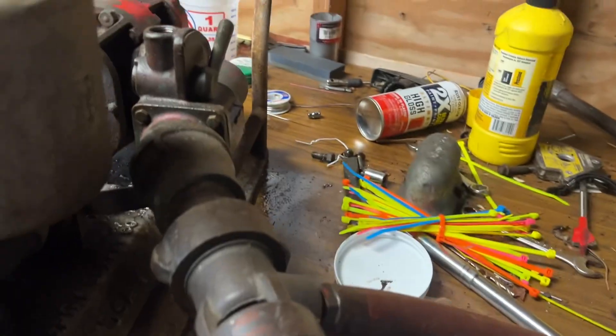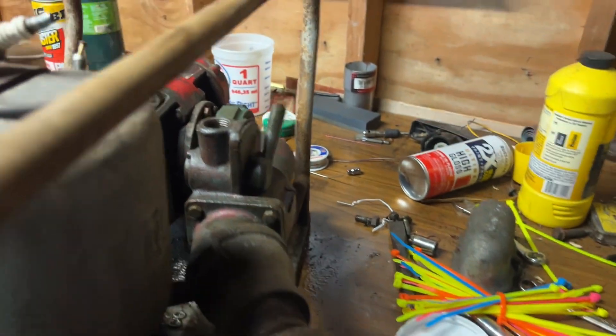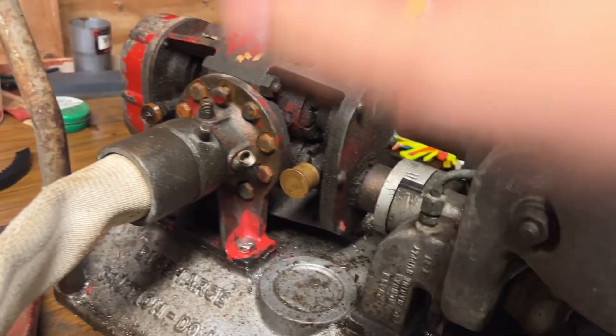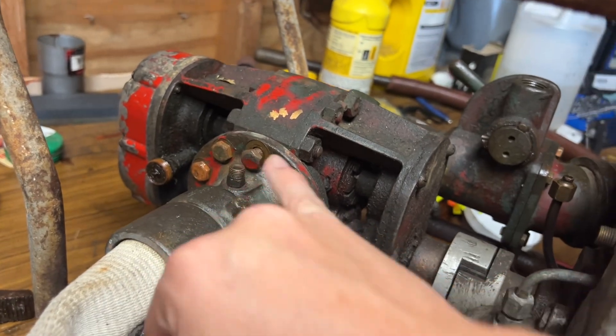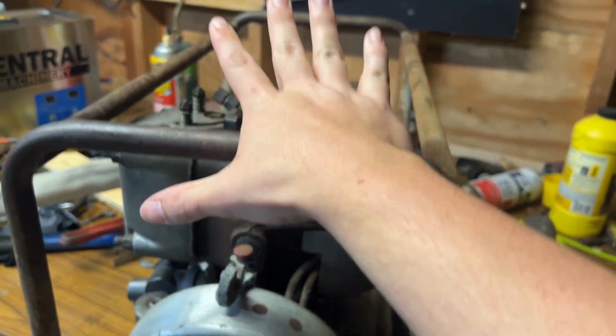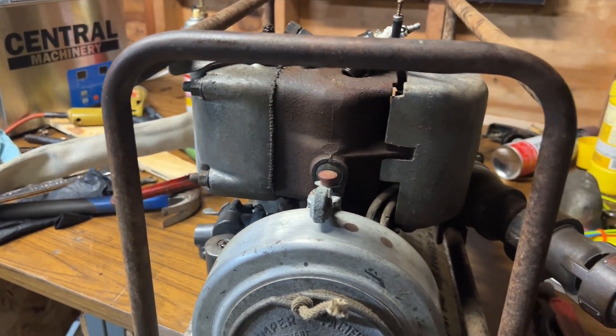In a jiffy, you've got your suction hose here — it's reinforced hose — and you can add firefighting foam. This is 60 gallons per minute, 100 PSI at full bore. What this is going to do is feed water into the block, routing the exhaust down into the base and then out through that port.